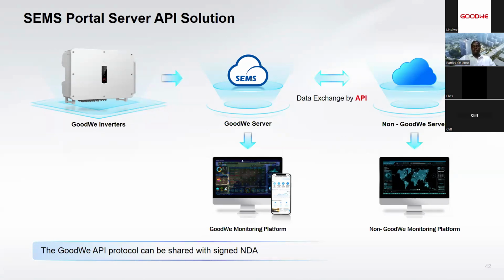Now, in case you have a third-party monitoring portal that you would prefer to display your PV installation data, the GoodWe server is capable of integrating with the third-party server using the API protocol. The mostly used protocol is the Open API. Now, the same server will be able to push data of the generation or of the plant to the third-party server. And in respect, you'll be able to see the plant generation through the third-party monitoring portal. Now, this is a feature which is actually becoming a hot topic, just to integrate with the various upcoming monitoring portals within the market.